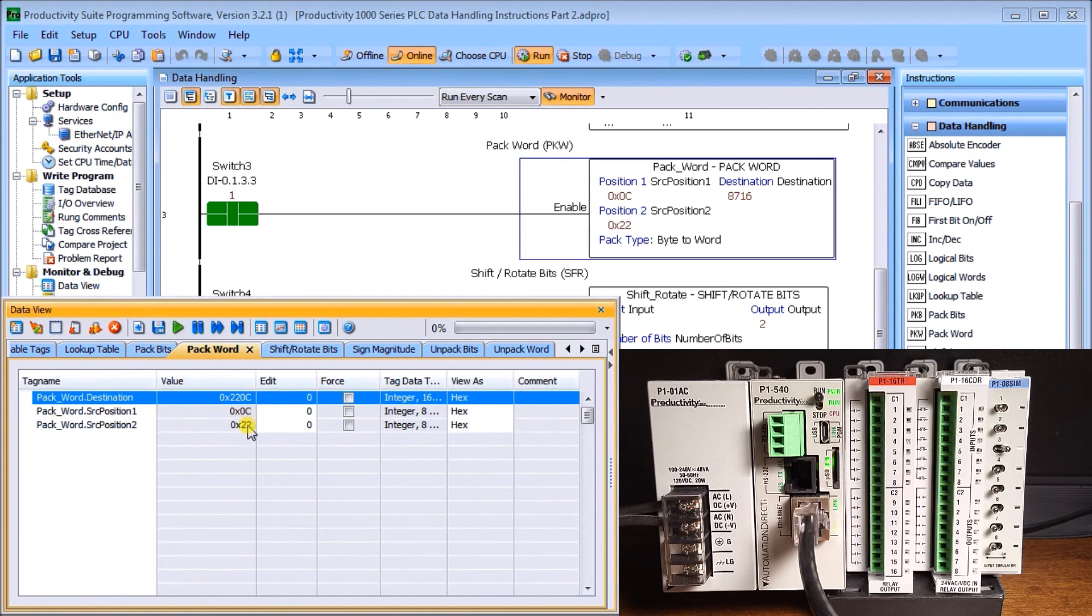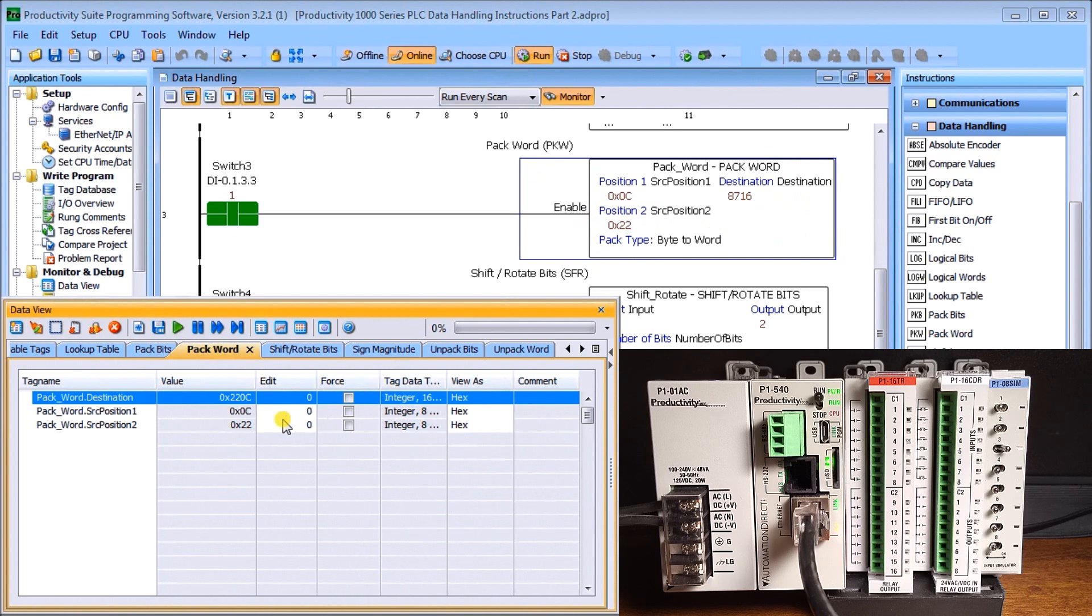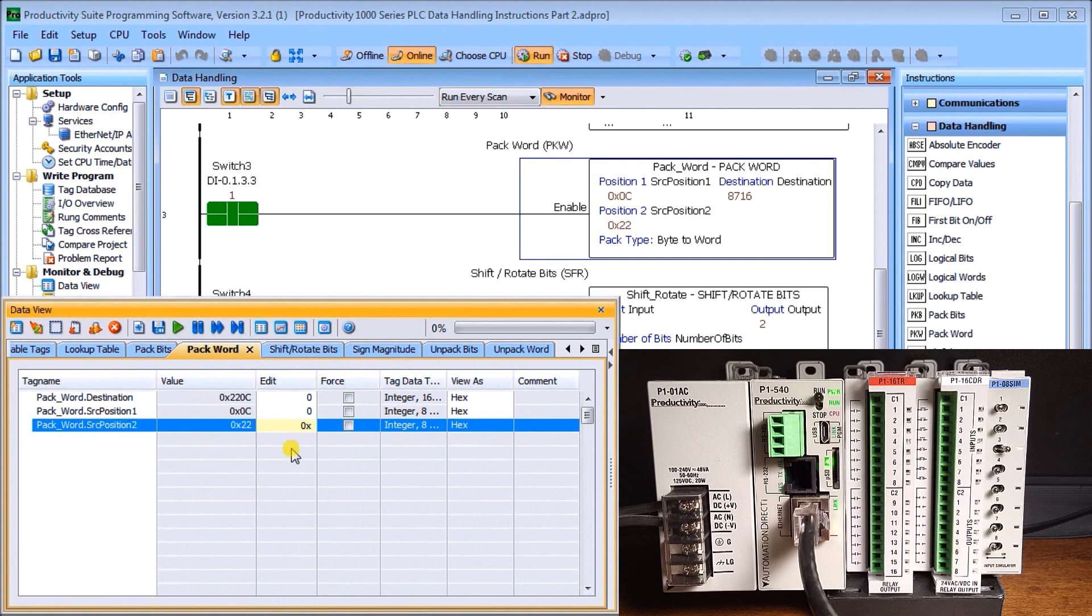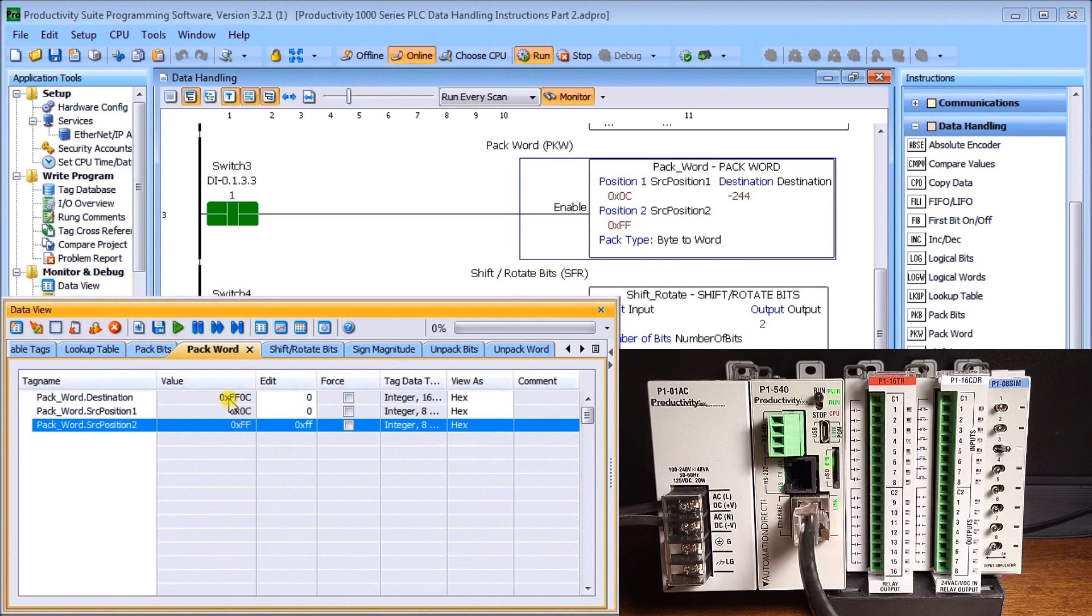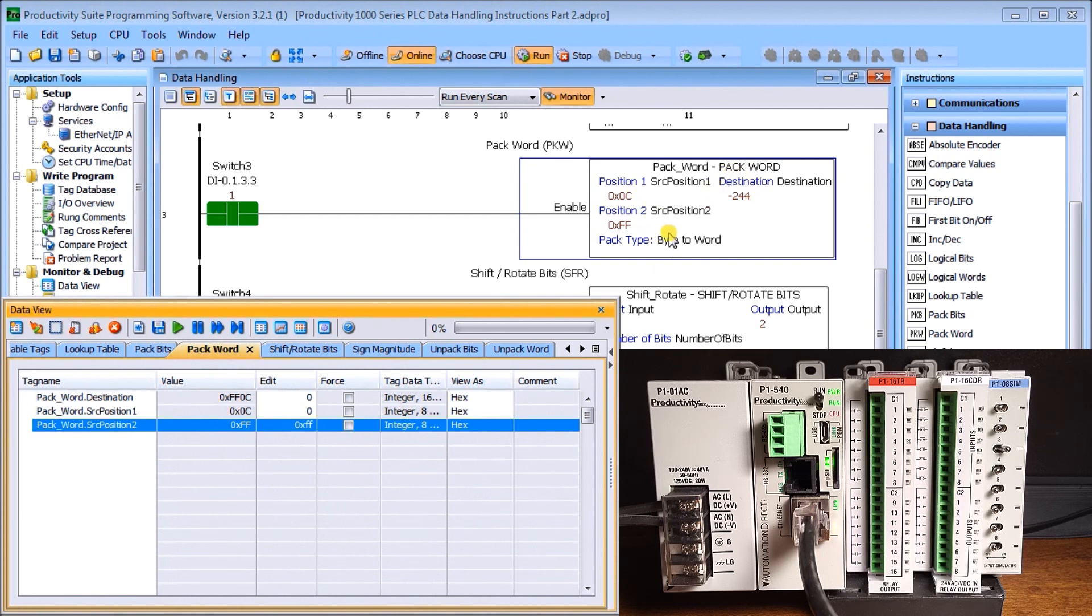Let's call up data view and change that to hex. In my instruction, I said my least significant word is in position one, so this is 0C, and my most significant is 22. Every time switch number three is on, it combines those two together into one destination word. The destination word is now 220C. If I change any one of these, let's edit this and change this to FF and write that. Now it changes to FF0C. This output on my ladder is represented in decimal. That's the pack word instruction.